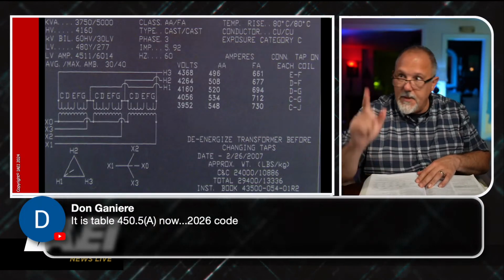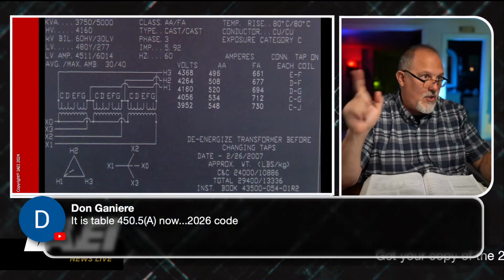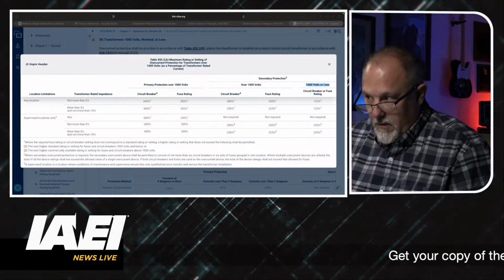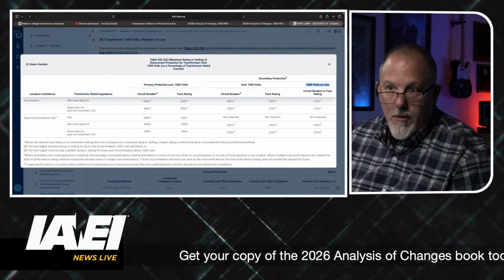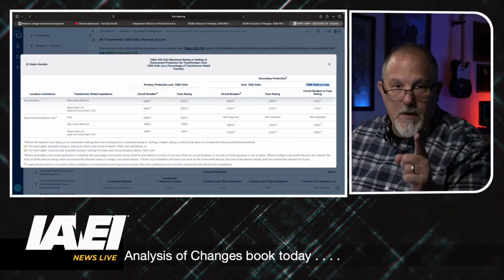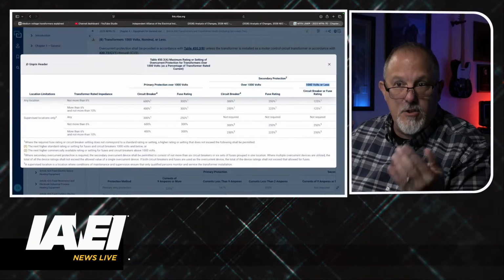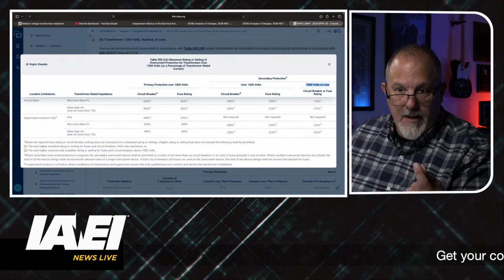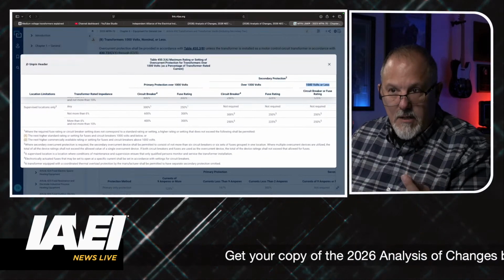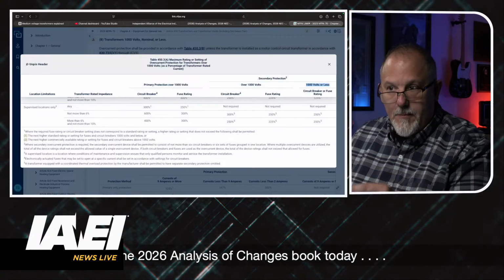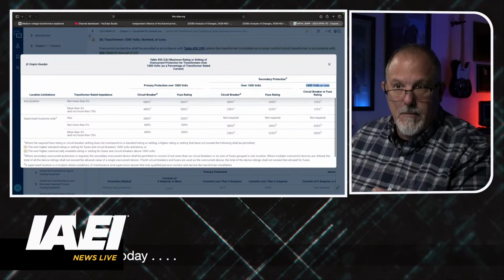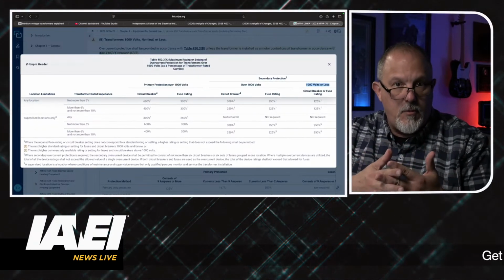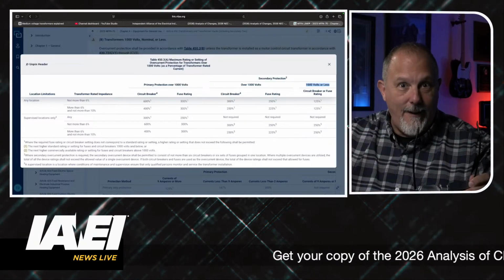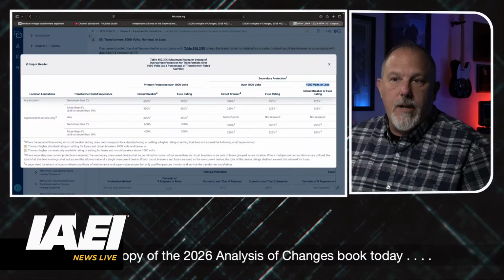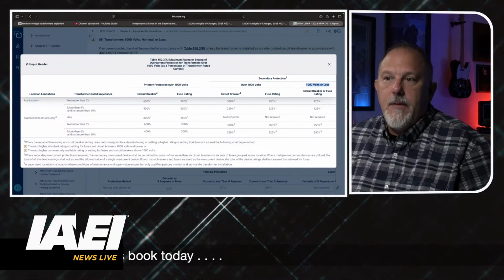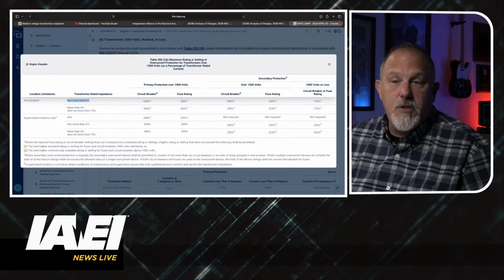Okay, so, but in any case, my impedance here is 5.92, and in this table, it has not more than 6% impedance, so I would follow this line item, any location. If I'm in a supervised location only, a supervised location is a location where conditions of maintenance and supervision ensure that only qualified persons monitor and service the transformer installation. So they give you in the informational note a little bit more information regarding that supervised location.